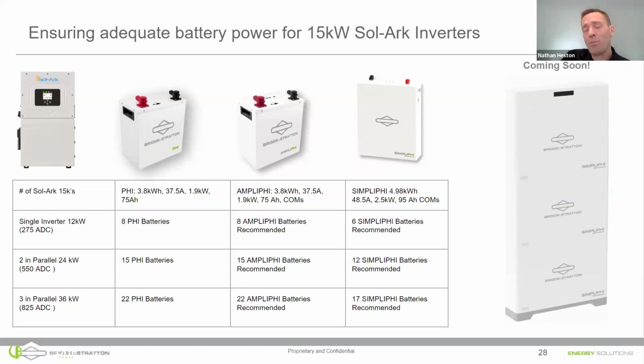However, if you have a small draw on your system, you could use an undersized bank, just knowing that in a grid down situation, you're not going to be able to power all of your loads. Okay, so there are a lot of variables to that question. I hope I've done it justice. We can talk more about it at the end. But there are some minimum sizes that we would recommend for this inverter.